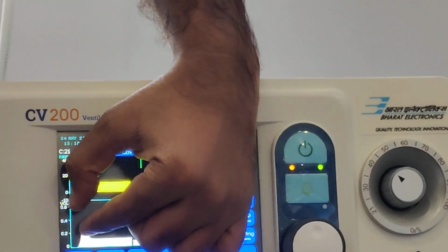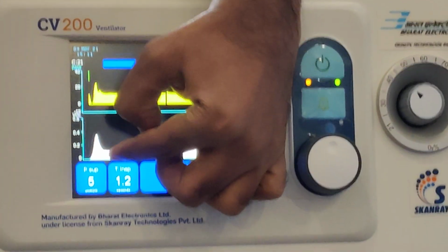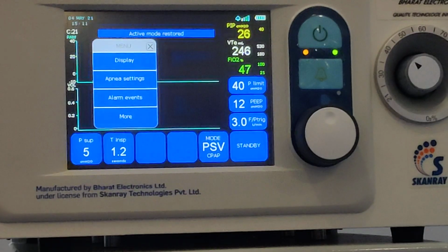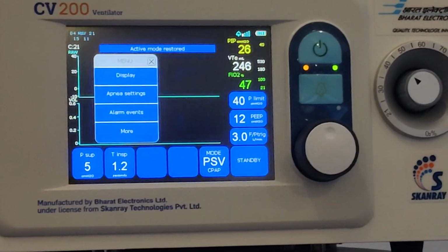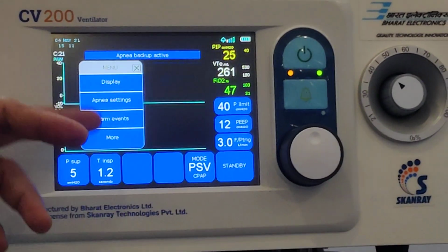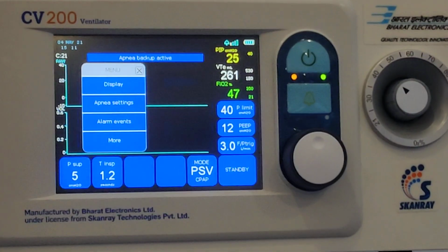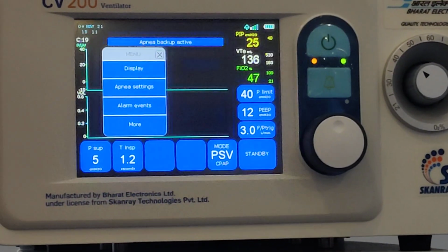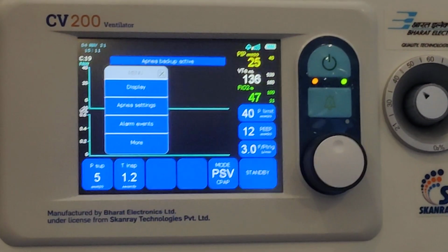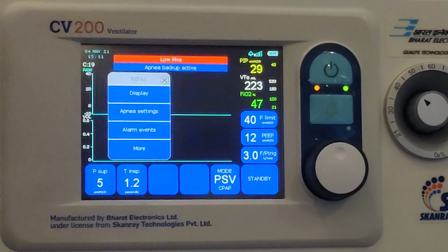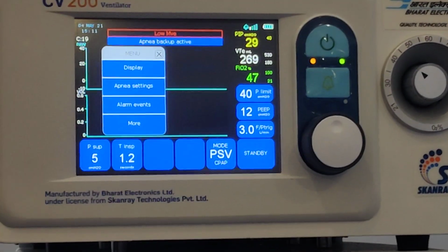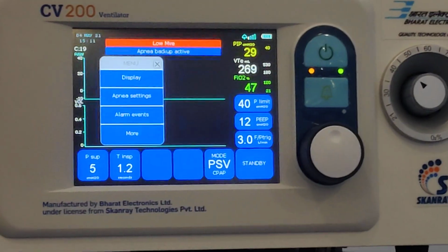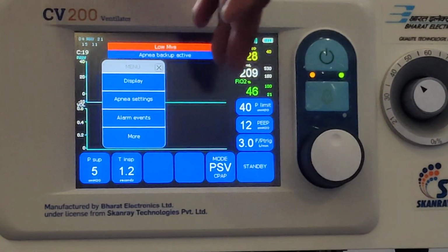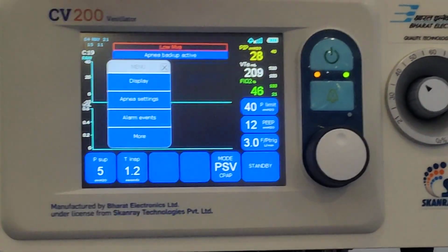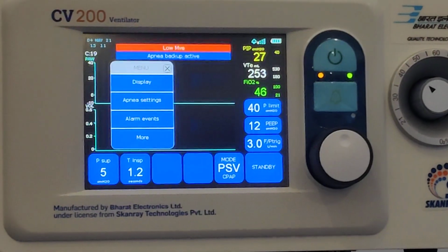See this. You're getting this volume back in the ventilator, but the remaining volume is leaking from this leaky connector. So if there is no proper equal-shaped mountain, that means there is some leakage happening somewhere. So watch for a proper mountain shape in the volume time scalar. It's an easy thing to do if you're not getting numbers properly, or if you don't want to read the numbers. This is an easy thing to see straight away.